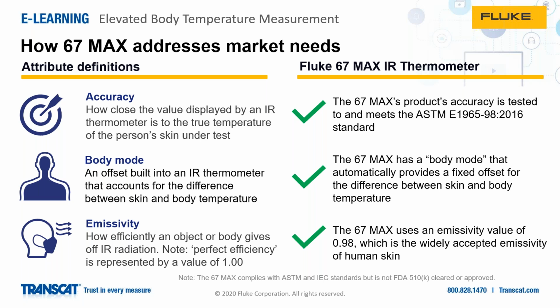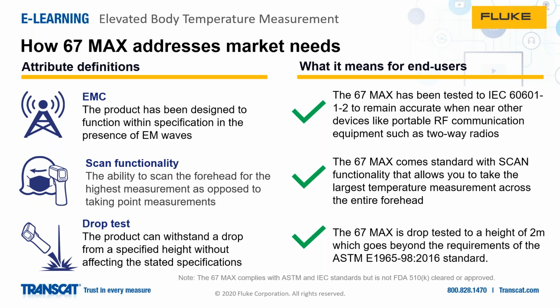So looking at those attributes that we discussed before, how does the 67 meet those? Well, the 67 Max product accuracy is tested to and meets the ASTM E1965-98 standard, as we've discussed before. It has the body mode that automatically provides a fixed offset between the skin temperature and the body temperature. And then we use that emissivity value of 0.98. EMC has been tested to the IEC 60601 standard to remain accurate when near other devices that you might find yourself around, such as portable RF equipment and two-way radios. We do have the scan functionality that allows you to hold the trigger down and scan across the entire forehead for the hottest temperature. And then the product itself is drop tested to a height of 2 meters, which goes beyond the 1 meter outlined in the ASTM standard.